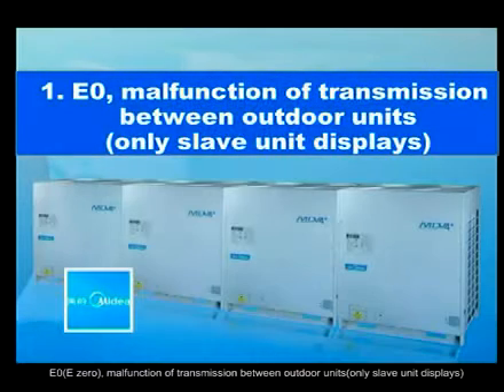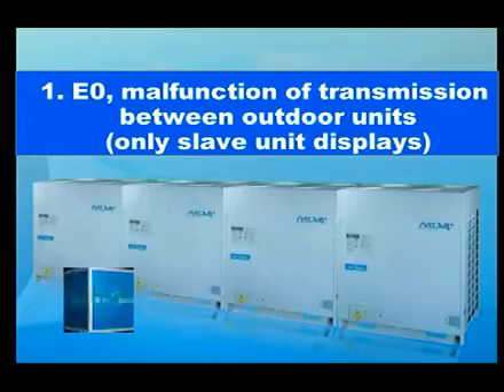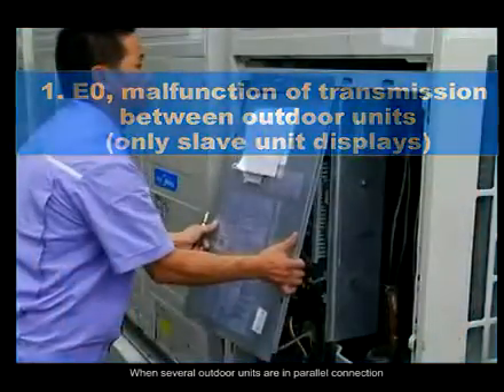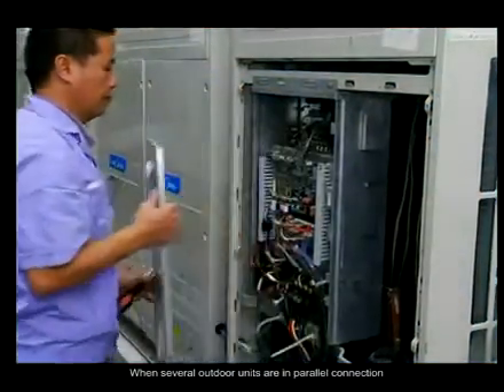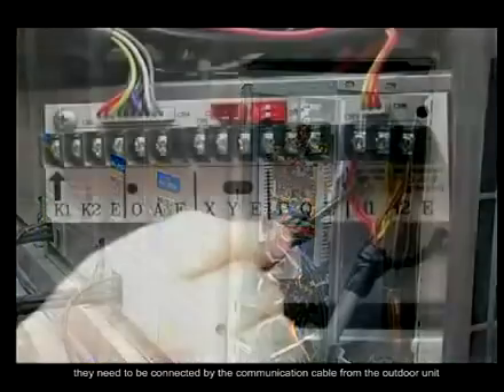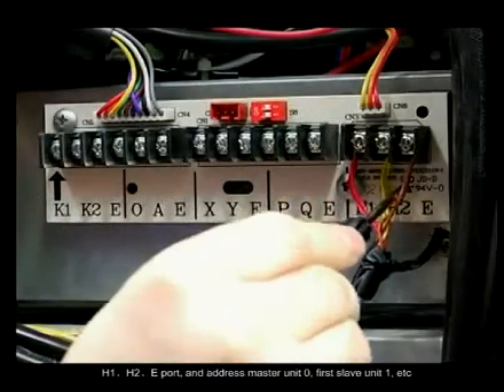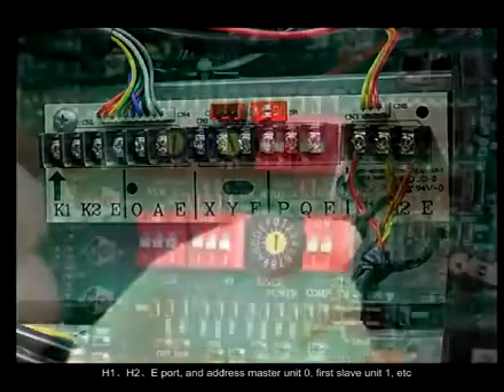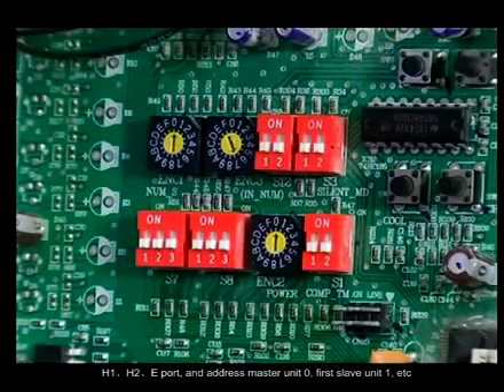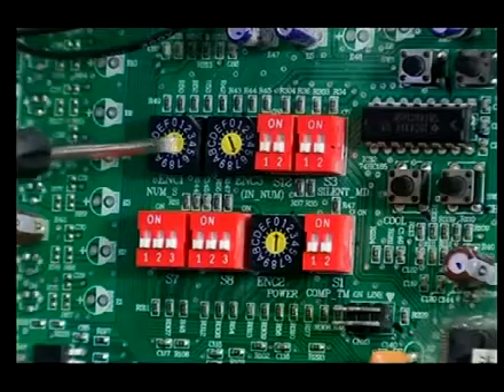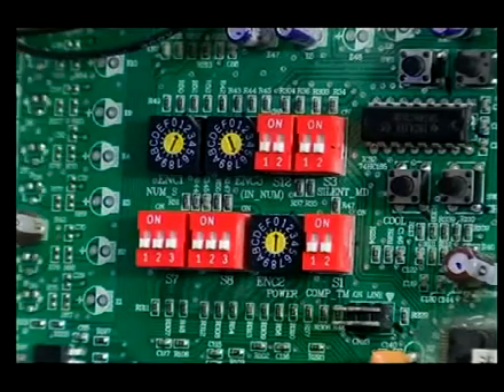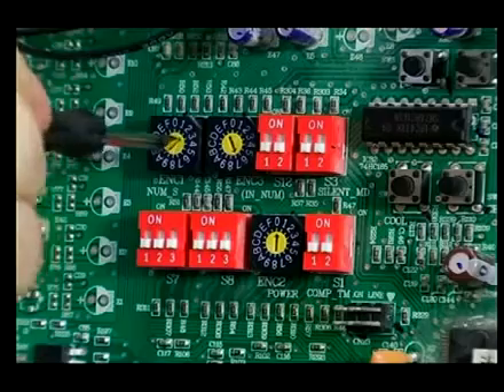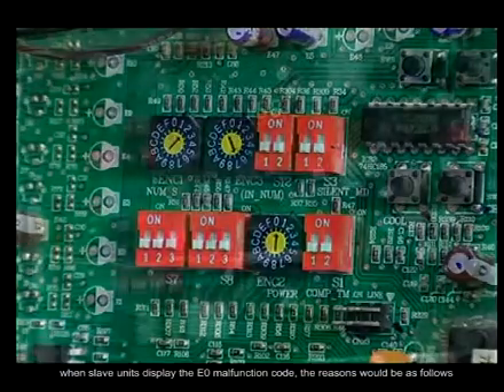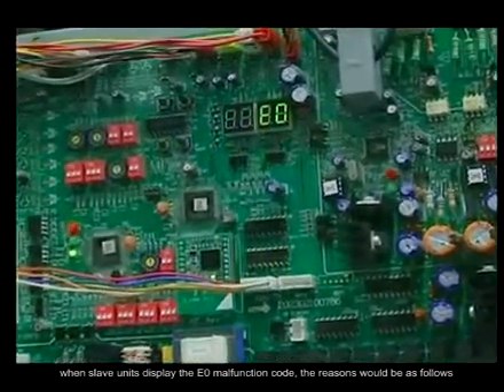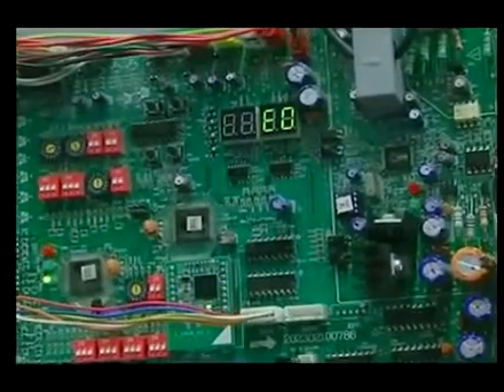E0. Malfunction of transmission between outdoor units. Only slave unit displays. When several outdoor units are in parallel connection, they need to be connected by the communication cable from the outdoor unit H1, H2, E-port, and address master unit 0, first slave unit 1, etc. When slave units display the E0 malfunction code, the reasons would be as follows.